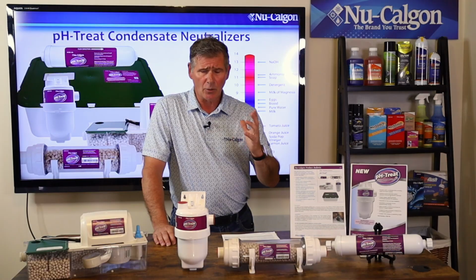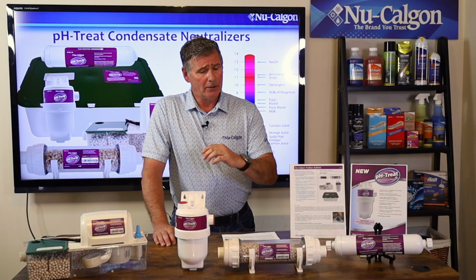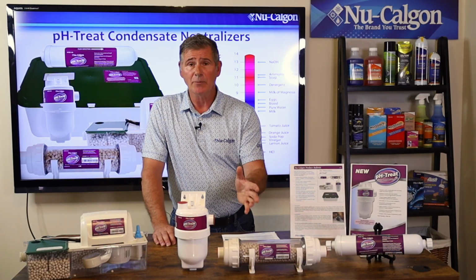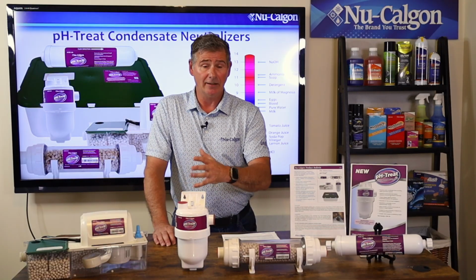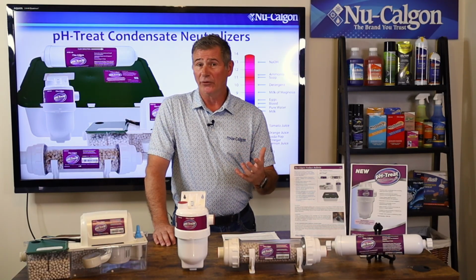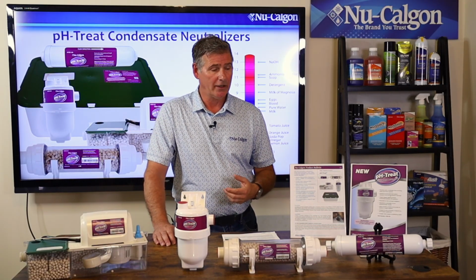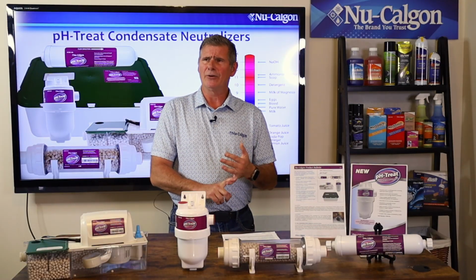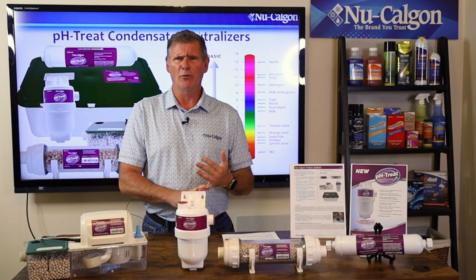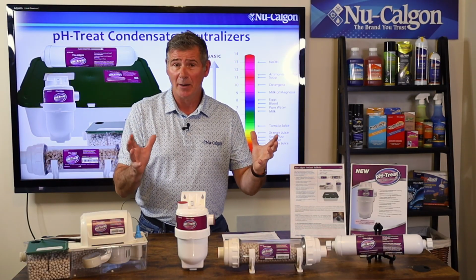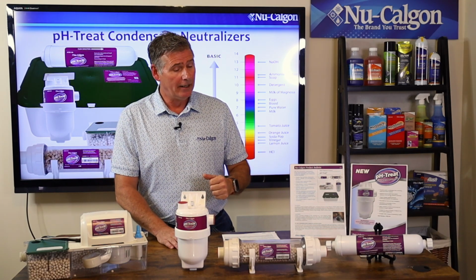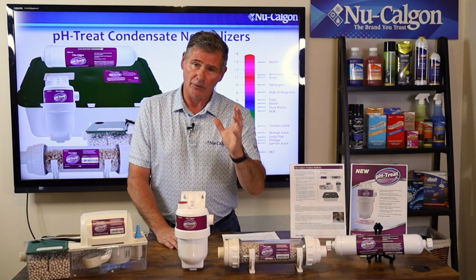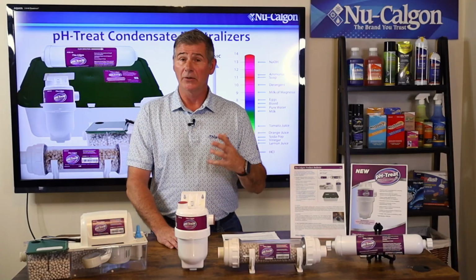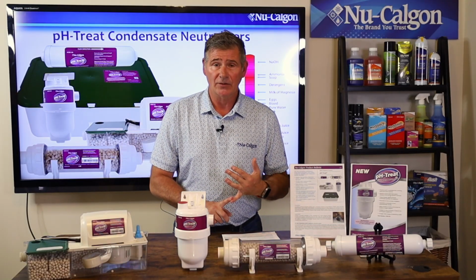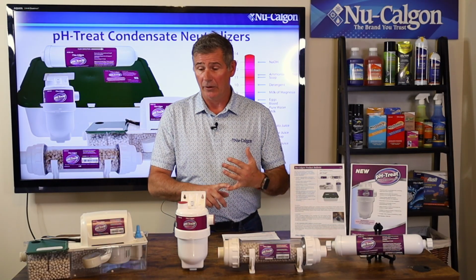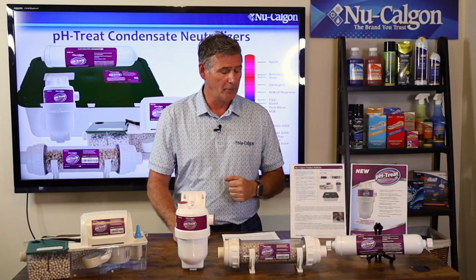So you're going to want to check your local codes, because there are codes that require some type of condensate drain line neutralizer on those systems in particular areas around the country. And again, you're going to want to check that. I believe the International Plumbing Code is code 803.1. I don't know why I remember that, but I believe that's the code where it's a requirement that you have these on. So make sure that you check your local code, because there are fines and things like that that can be levied if you're not putting these systems on those types of appliances.